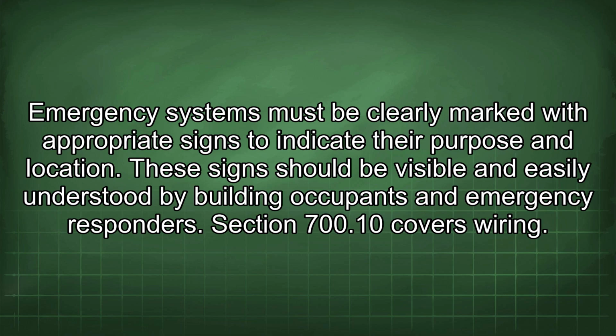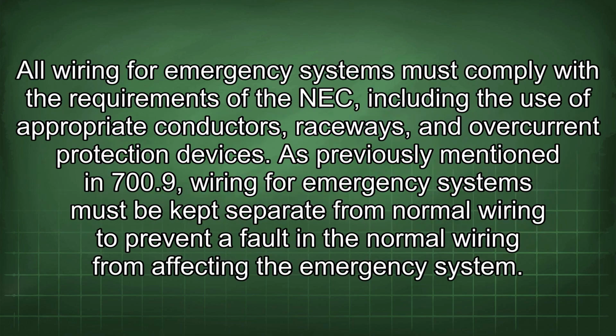Section 700.10 covers wiring. All wiring for emergency systems must comply with the requirements of the NEC, including the use of appropriate conductors, raceways, and overcurrent protection devices. As previously mentioned in 700.9, wiring for emergency systems must be kept separate from normal wiring to prevent a fault in the normal wiring from affecting the emergency system.